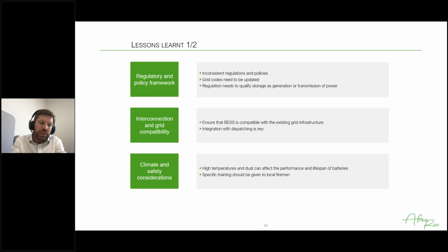Another important feature is integration into the grid, and in particular with the dispatching of the off-taker, which is absolutely key. If we want that system to work efficiently, the integration with the dispatching must be absolutely smooth, and they must have instant control over the batteries. The batteries should discharge or take off-set power automatically, but also at the demand of the dispatcher, and it should be done within seconds if we want to provide the service.